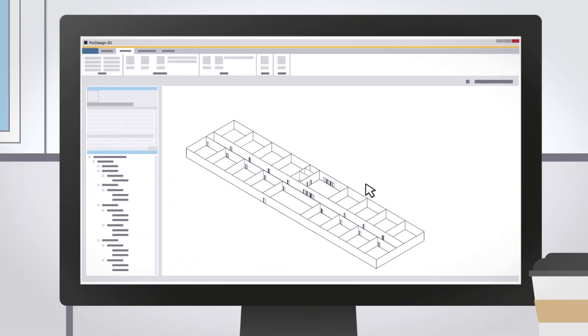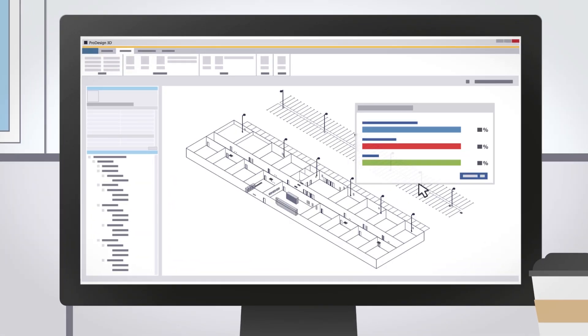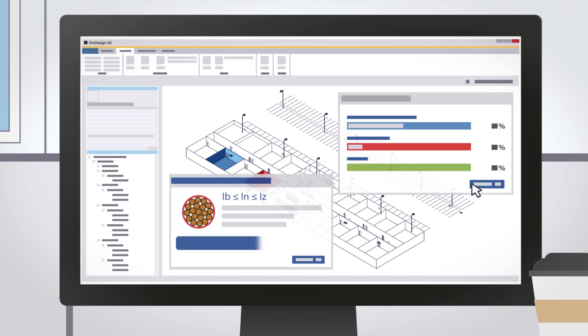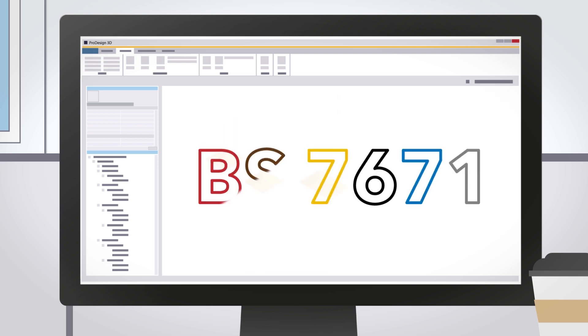While your design is progressing, you can perform calculations on your project at any point to check what your cable sizes and circuit-protective devices are by using the property dialog in Revit to ensure BS7671 conformance.